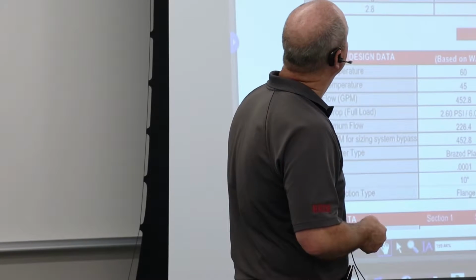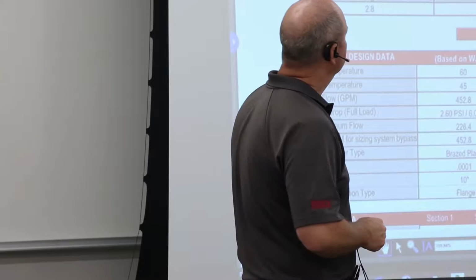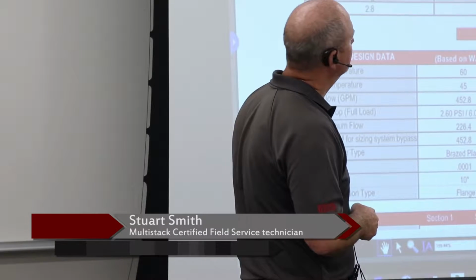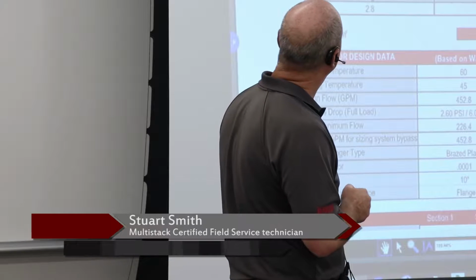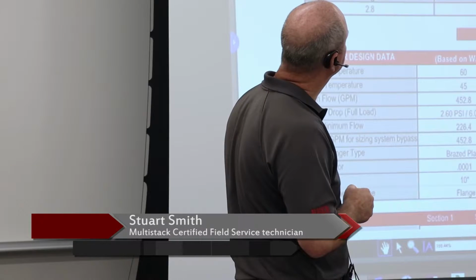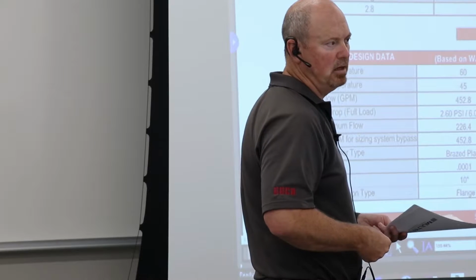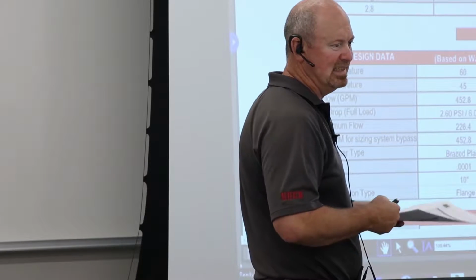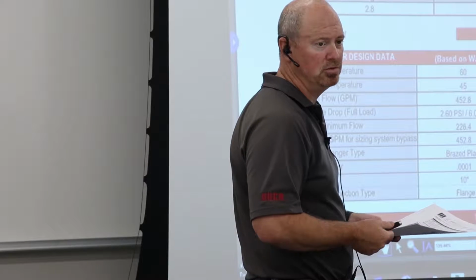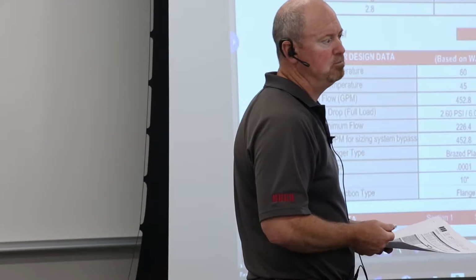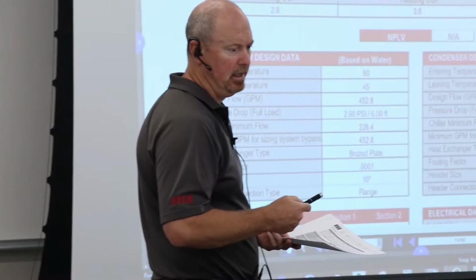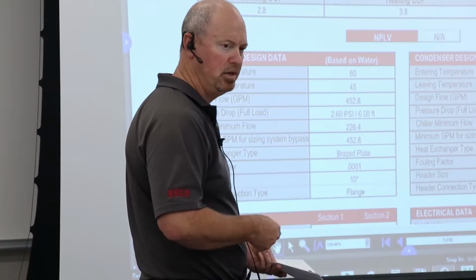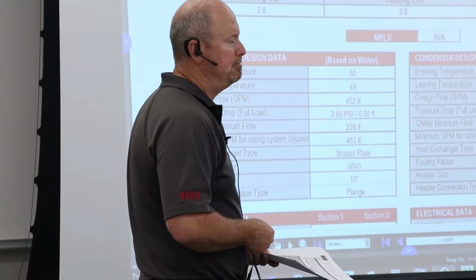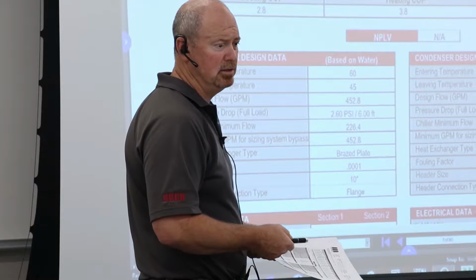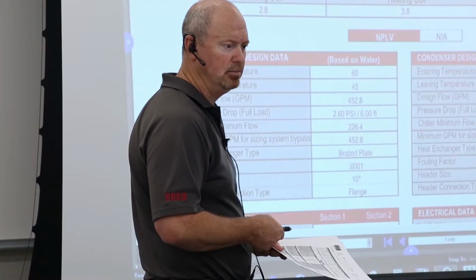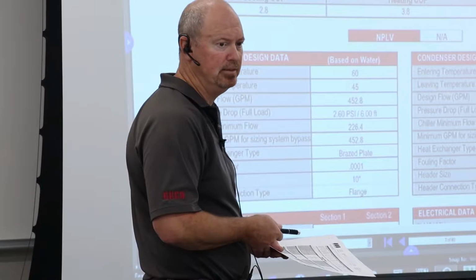Okay, so what you have purchased here is a Multistack. You got 3 quads, a total of 283 tons. If you don't have at least 8% calling at a time, then you won't see anything running at all. You'll need at least a heat load on the cool side or the heat side. In the wintertime, you're actually going to be running in cooling. In the summertime, you're going to be running in heating for dehumidification and reheat purposes.